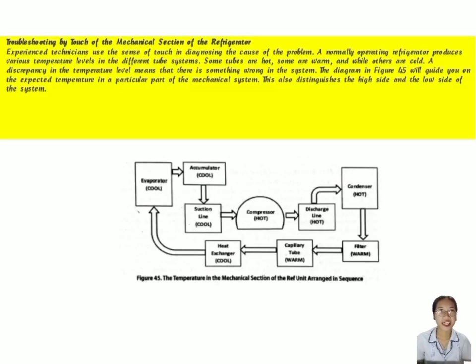Troubleshooting by touch of the mechanical section of the refrigerator. Experienced technicians use the sense of touch in diagnosing the cause of the problem. A normally operating refrigerator produces different temperature levels in different tube systems. Some tubes are hot, some are warm, and others are cold. A discrepancy in the temperature level means that there is something wrong in the system. The diagram in figure 45 will guide you on the expected temperature in a particular part of the mechanical system. This also distinguishes the high side and the low side of the system.